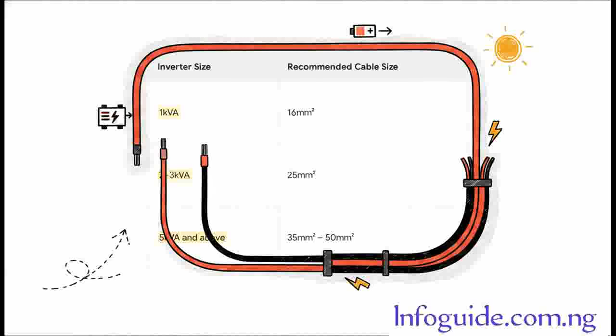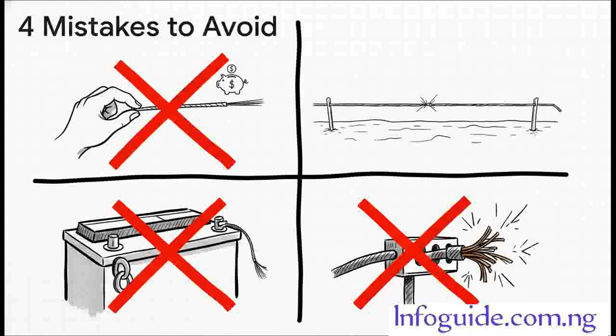First up, trying to save a few bucks on a smaller wire. It's a false economy that'll cost you way more in lost power down the road. Second, forgetting to account for distance. A long run needs a thicker cable, period. Third, and this is a big one, never use your leftover solar panel wire for your batteries. It just cannot handle that massive current. And finally, a poor connection. Even the perfect cable is useless if it's not securely terminated with the proper lugs.